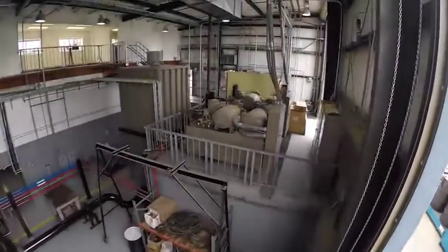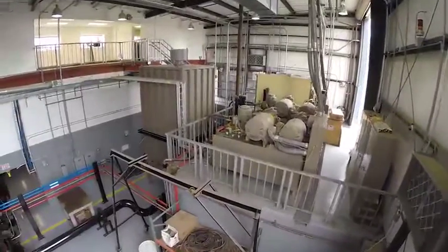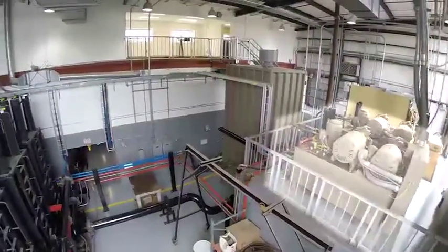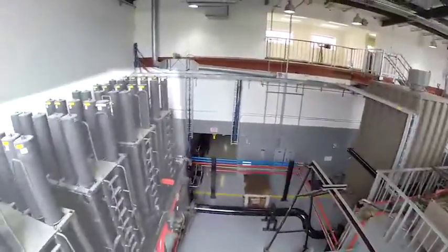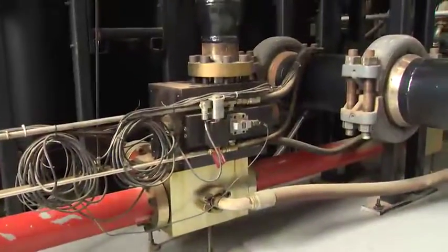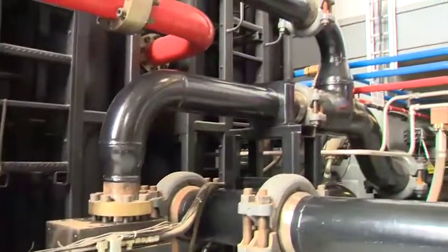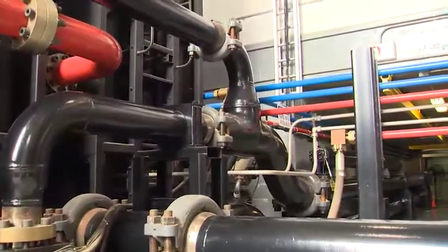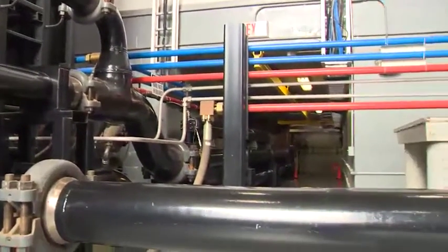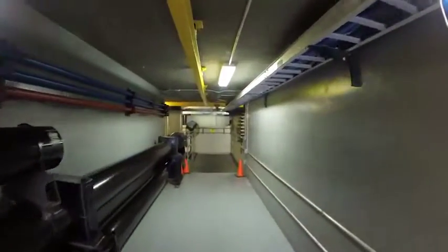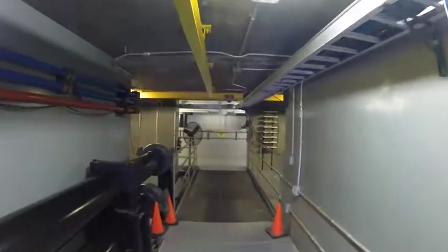The hydraulic power system is shared by all test equipment at the NHERI site. It consists of 2 hydraulic pumps, a surge tank, an accumulator bank, a pressure regulating valve, and a hydraulic piping system. A cooling tower and electrical power substation are located outside the building. A service tunnel connects the hydraulic power and control system building to the LH Post.